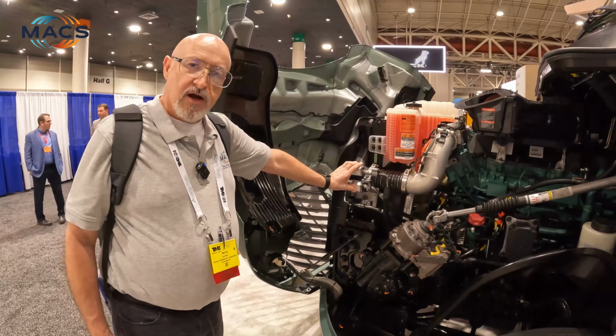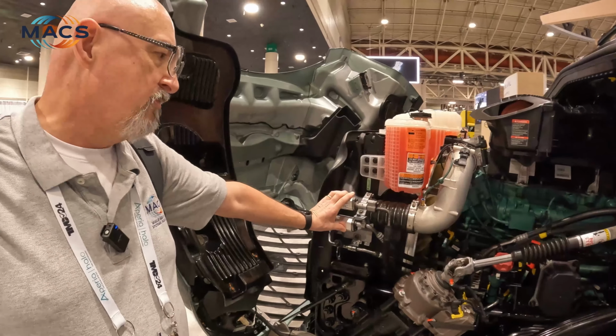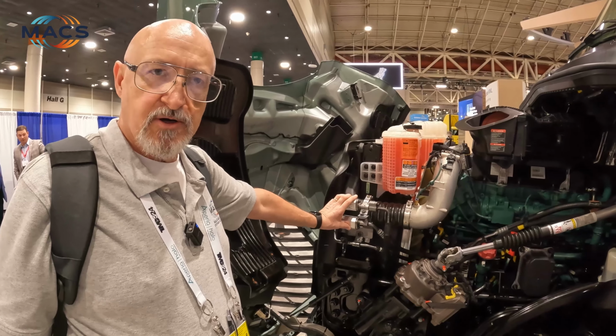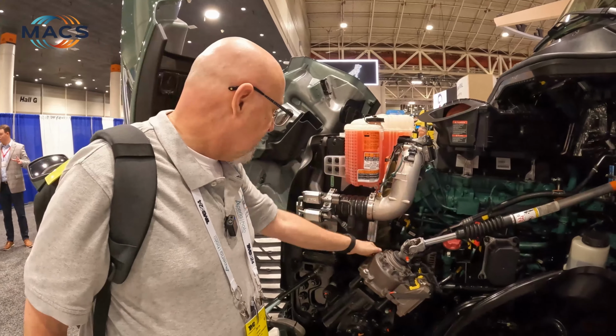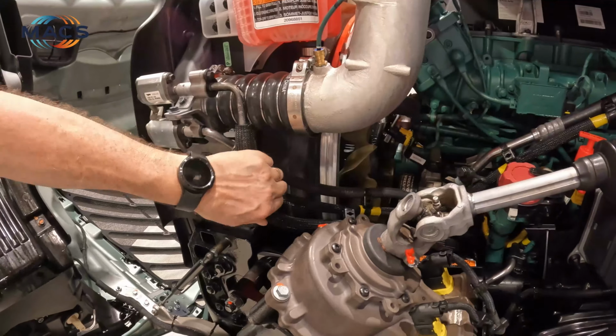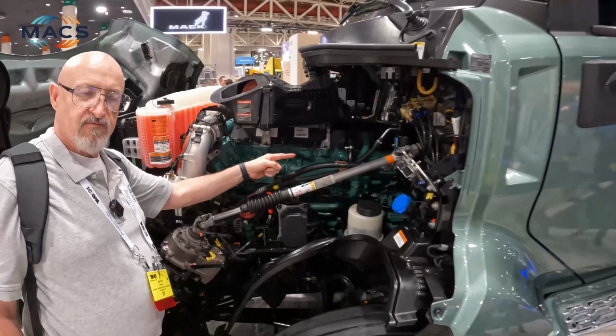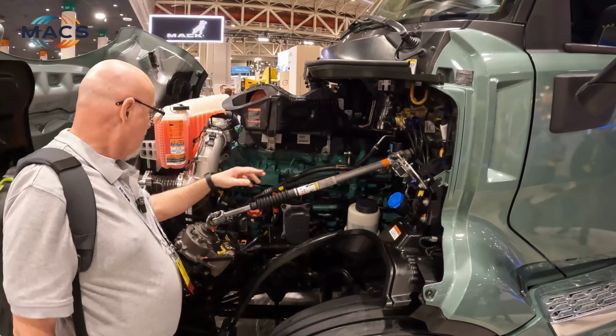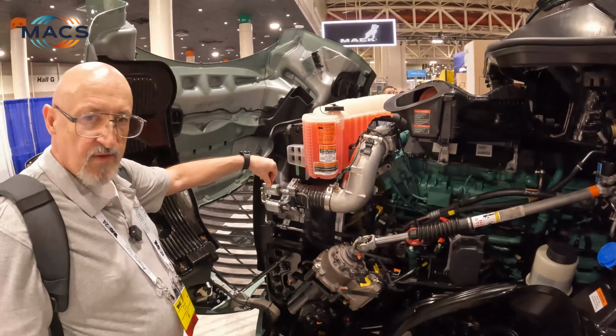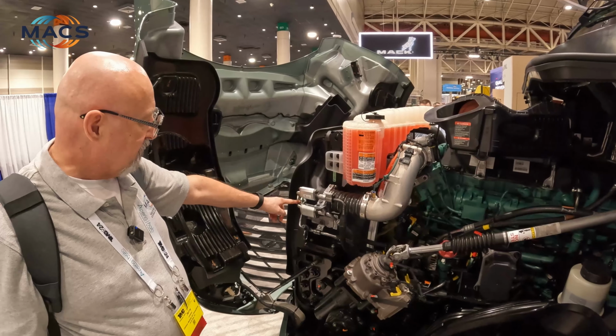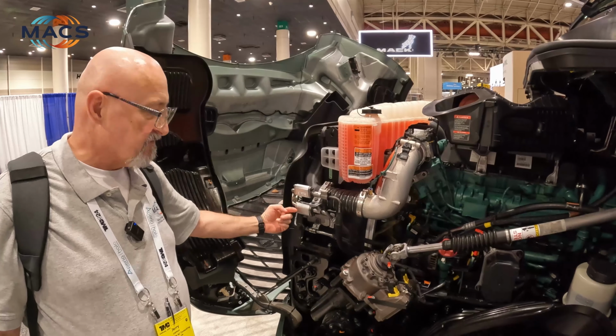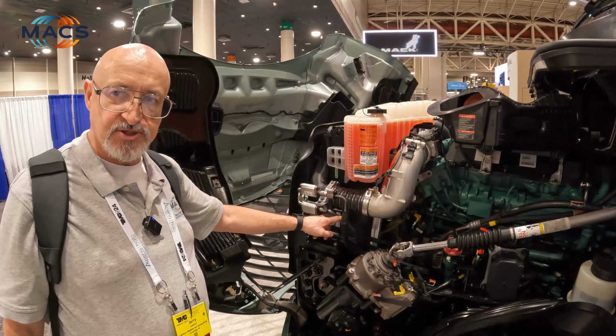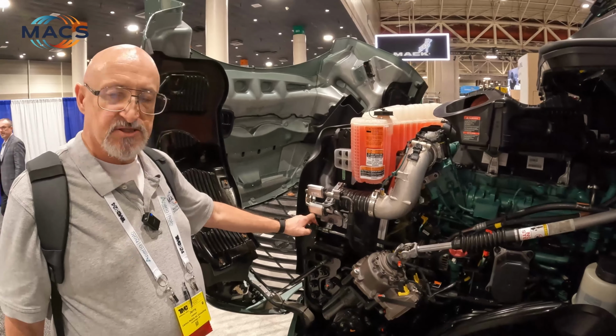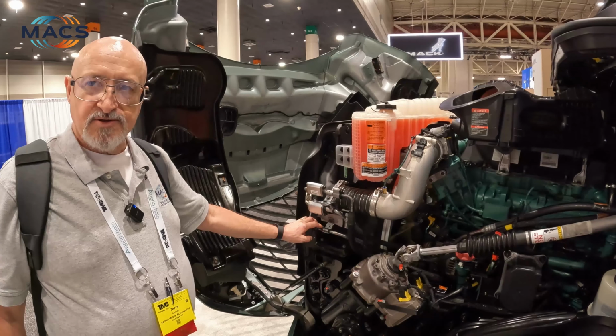So these check valves are basically there to allow one-way flow for the high pressure gas going to the condenser. This line goes down, hits the rail, goes all the way back to the compressor under the cab, the 24 volt DC electric compressor, and that'll flow here when the engine's off. So you'll only get one-way flow. The reason the check valve is on it is so that it doesn't flow back to the engine compressor, or vice versa, when the flow reverses. Everything else is basically exactly the same, so there's no different systems needed to do that.